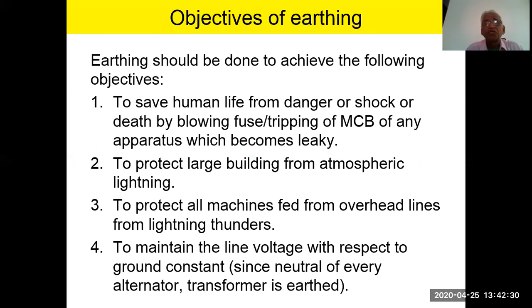Now, objectives of earthing. Earthing should be done to achieve the following objectives: to save human life from the danger of a shock or death by blowing the fuse or tripping the MCB of any apparatus which becomes leaky or faulty, to protect large buildings from atmospheric lightning, to protect all the machines fed from overhead lines from lightning thunders, and to maintain the line voltage with respect to the ground constant, since the neutral of every alternator and transformer is earthed.